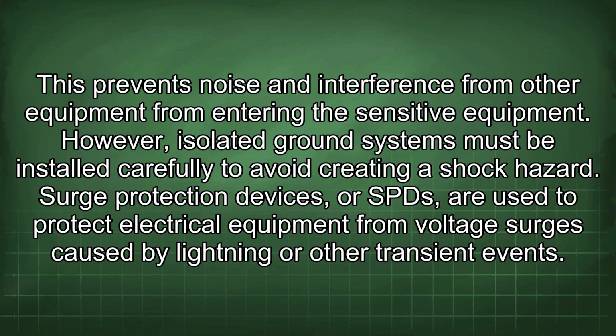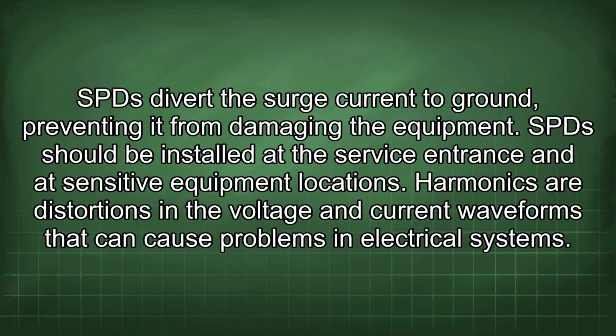Surge protection devices, or SPDs, are used to protect electrical equipment from voltage surges caused by lightning or other transient events. SPDs divert the surge current to ground, preventing it from damaging the equipment. SPDs should be installed at the service entrance and at sensitive equipment locations.